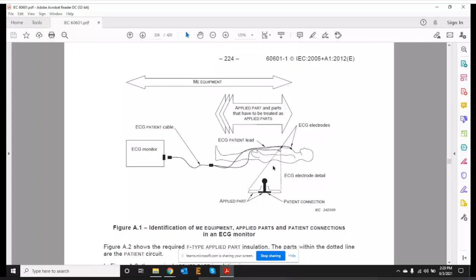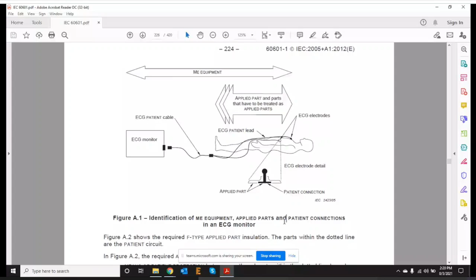If you see the old ECG devices, they used to touch the skin of the patient. This touch of the skin is also to be tested. They should not give too much voltage to give a shock in that particular area, or the flow of current in that particular area. So the two terminals which are there for the ECG monitoring should not give the patient a shock, or a very high current should not flow from that particular path, beyond the rated current.